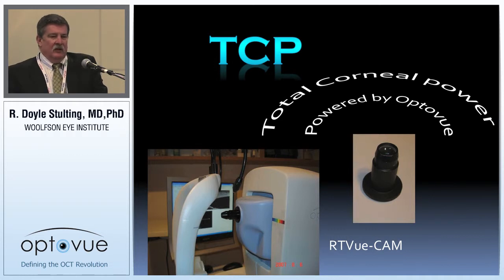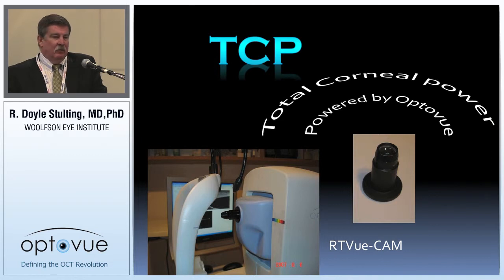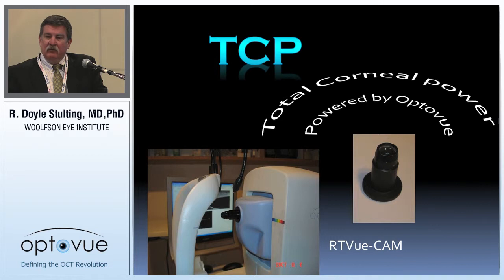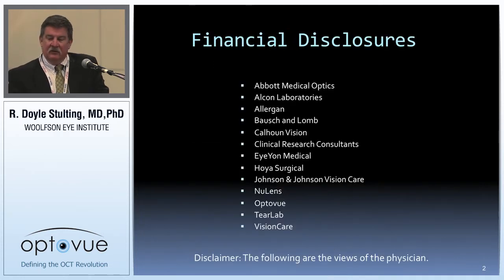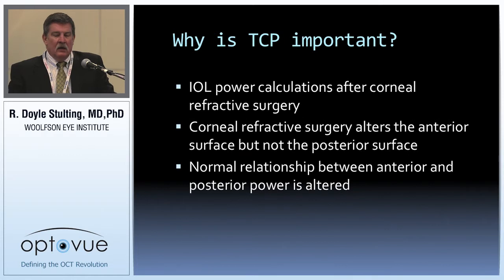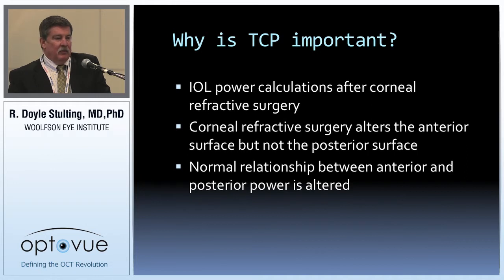Most of you know that the cornea has two refractive surfaces: the anterior surface and the posterior surface. Traditionally, we used keratometers to measure corneal power. The keratometer made a couple of assumptions — one is that the corneal power was consistent across the surface, so that measuring at a diameter of about three millimeters could be generalized to the entire cornea. That measures the anterior corneal power, and we have to make assumptions about the posterior corneal power and the distribution of the curvature.